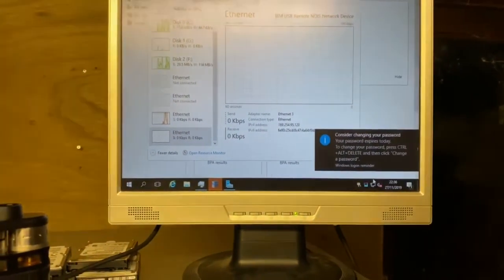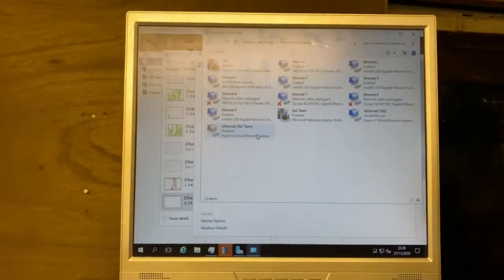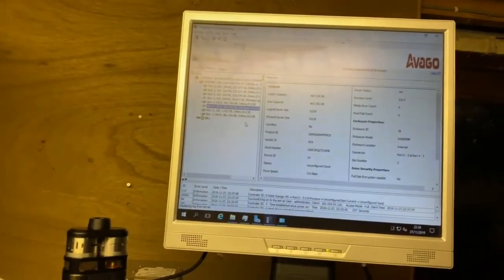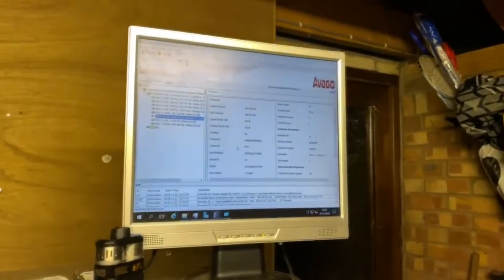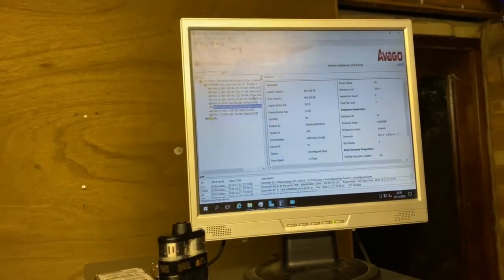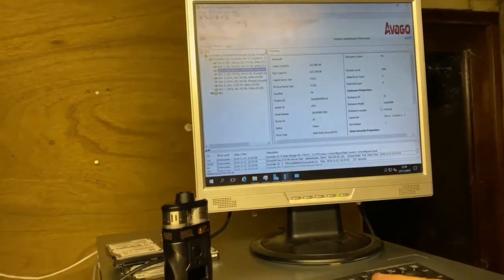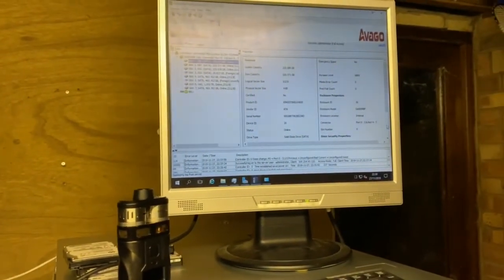So why is our team of normal NICs disabled. Interesting I guess. So let's see if that orange light is gone. It has. So it must have just assumed that it failed. So that's weird. I'm not entirely sure how we check the firmware version. Is it running everything at 6 gigs per second? It is. Temperature is 0 degrees. What temperature is it? It is 8 degrees. So that's I guess about right. Are there any of us reporting temperature? 13 degrees. That seems a bit more normal. Right. What is this saying? What is our firmware at? 2014. So that's going to need a good update.